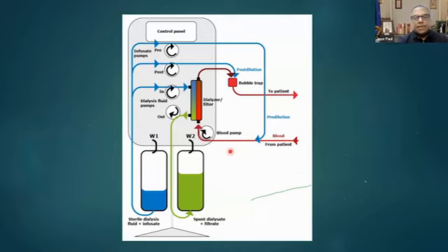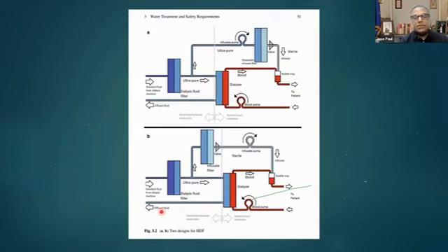However, these methods are limited by the amount of fluid that can be removed by ultrafiltrate. So you have to run a lot of bags to produce the desired level of ultrafiltration or the convective clearance that is required if you want to do hemodiafiltration. This is a major limitation if you use preformed dialysis solution in preformed bags. The solution for this problem is to generate the dialysis solution by the machine itself.